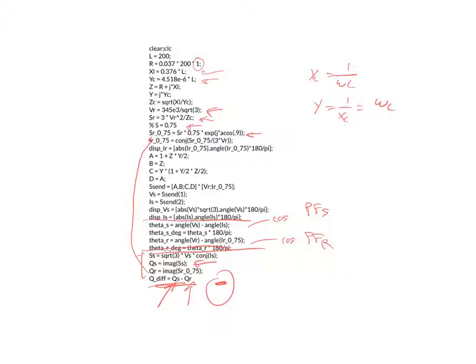The QR is greater than the QS. So if I've got a line here, I've got some Q in and some Q out. Q out is greater than Q in. I have to put additional reactive power someplace else. That's from the line. And it only applies because in this case, we have a lower value of loading than the SIL.